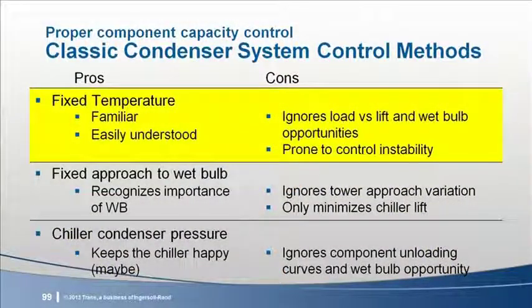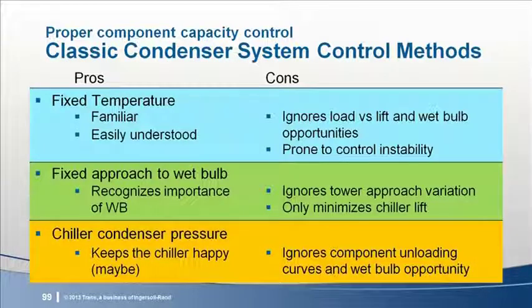First, they are all based on some single fact that has been improperly stretched into an optimizing philosophy. Here are a few examples of what I'll call these improper "so" statements. The system is designed with an 85-degree entering condenser water temperature, so that must be the right place to run it. The chiller benefits from cooler condenser water, so let's set the condenser water temperature set point to 55 degrees and give it as cool as possible. The tower is selected with a 7-degree approach, so it should run according to that. And finally, the chiller has a minimum allowed refrigerant differential pressure, so that must be the best condition to operate it. I think you get the idea.